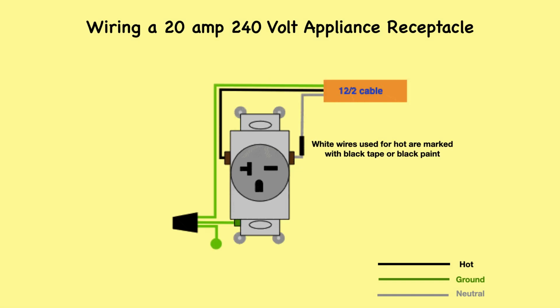This outlet is commonly used for a heavy load, such as a large air conditioner. The outlet should be wired to a dedicated 20 amp, 240 volt circuit breaker in the service panel using 12-2 AWG cable. With wiring a 20 amp 240 volt appliance receptacle, both the black and white wires are used to carry 120 volts each, and the white wire is wrapped with black electrical tape to label it hot. This circuit doesn't make use of a neutral wire, and the ground wire is connected to the ground terminal on the device. The slots are configured to accept only plugs from compatible appliances.